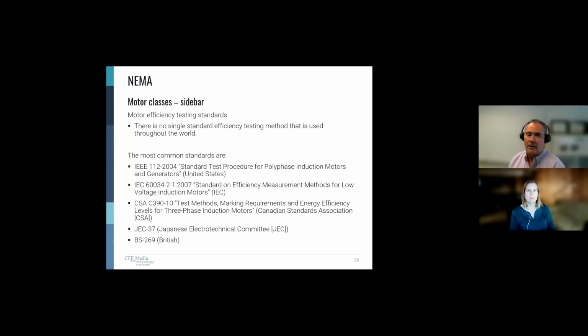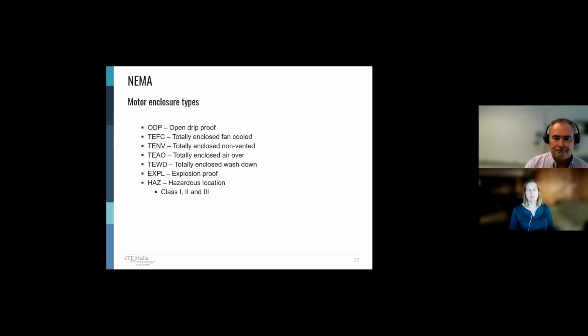All right, sidebar on efficiency. As with everything in the world, there is no single standard efficiency testing method. There's 5 we show right here. IEEE is a good one, IEC, CSA, JEC over in Japan, and then BS 269 in British. So just throw that out there: when you look at motor efficiency, just realize that depending on where your motor comes from, they're not all tested the same way. And that'll become important here in a minute.